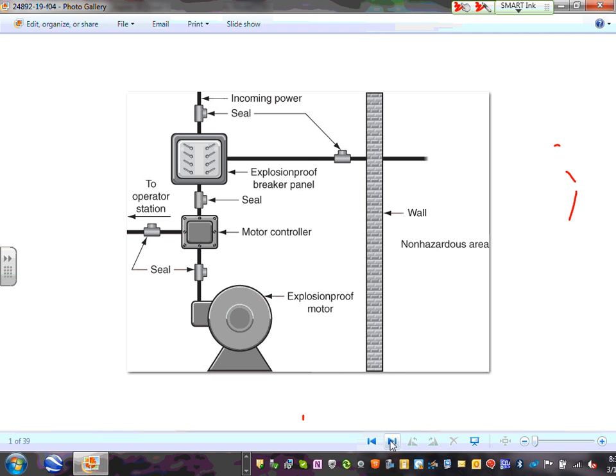I probably have seen a few of these. So our job, guys, as designers and engineers, we have no control over how they handle this equipment. That's not our job. Our job is to starve the fire from the ignition source. That's what we do. How do we starve it from the ignition source? We put our equipment in explosion-proof enclosures, so if it arcs and sparks, it's contained. That's all. I have no control over how they handle the gas, they have a whole industry handling the natural gas, but with coordination with them, we put special equipment there that cannot provide an ignition source for these gases and dust or fibers.